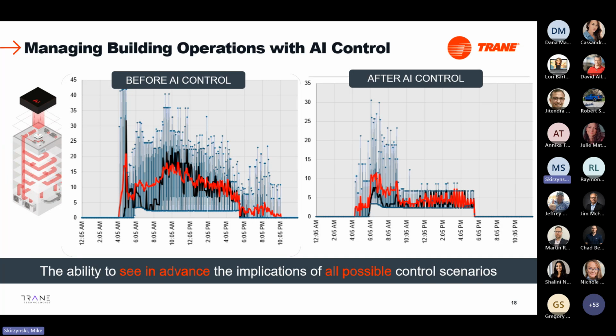A couple of things to note: first, the specific energy use for a piece of equipment is much tighter. Instead of activating 2 stages immediately or turning the fan to full speed, our algorithm modulates to maintain comfort while reducing fan wear, equipment wear and tear, and energy usage. Also, looking at the scales before and after AI control, it only spikes to about 30 kilowatts during startup, versus 45 kilowatts before AI control. That scale difference is dramatic, and that's where the energy savings really start coming into play, in addition to reduced equipment wear and tear.